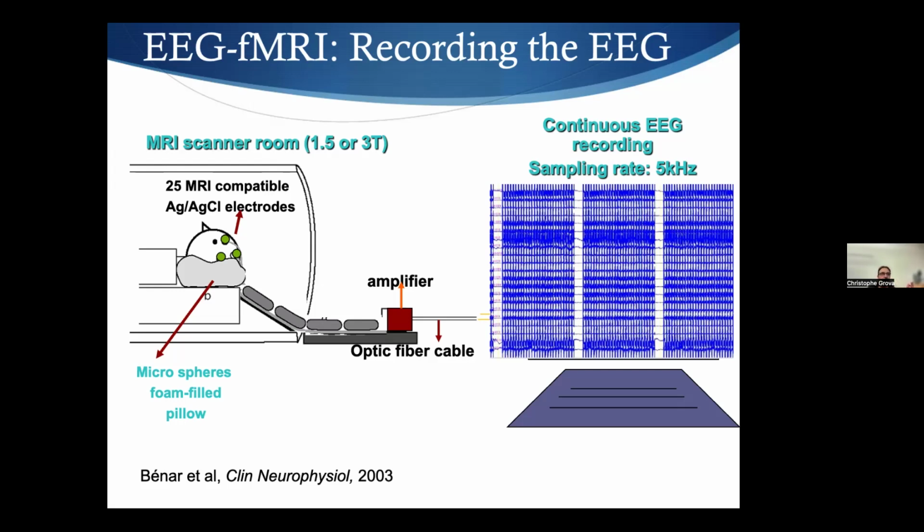So you need to take that into account. Not all systems are using that. I must say, with lots of experience in Jean Gotman's lab, where we use just standard electrodes, we never had any issues with heating or problems like that. At 7T, you'd better be careful. It depends also on the sequence. I remember for your study with MRS, because MRS is not depositing the same energy as a standard BOLD sequence, that's not my expertise, but I remember Makoto checked some aspects of that. So this might be important.